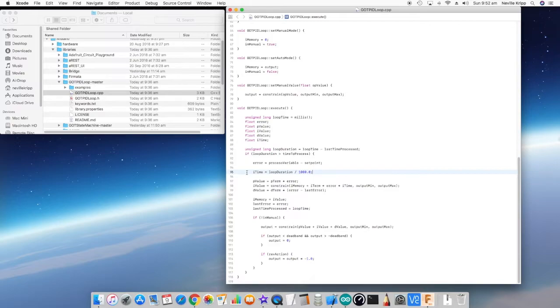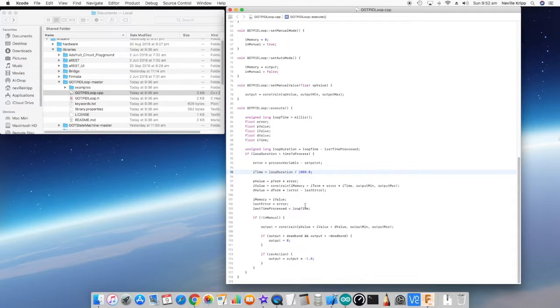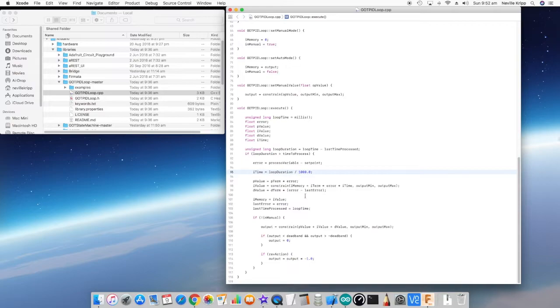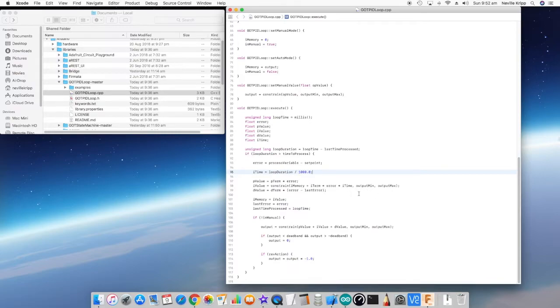The p value is a fairly straightforward calculation—it's the p term times the error. The i value is a combination of the existing i memory plus an integrated amount for the time period between loop processing, and we constrain that between the output min and the output max so we can't have the i memory effectively going outside of the output min and max and applying a huge integral.